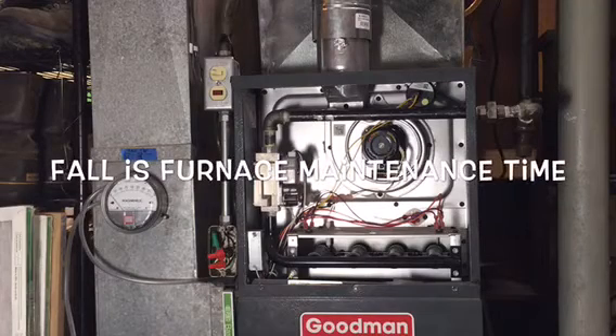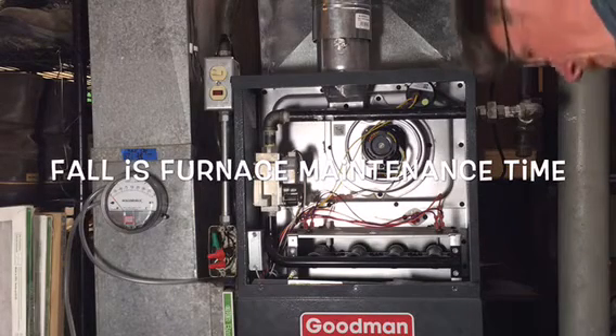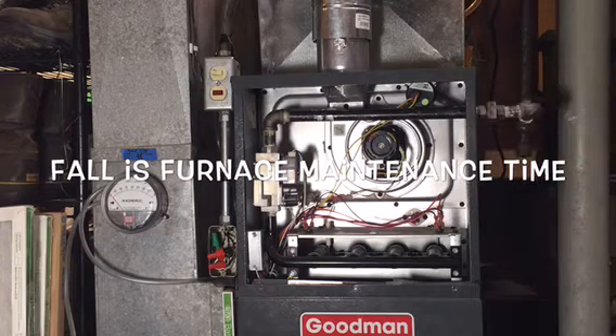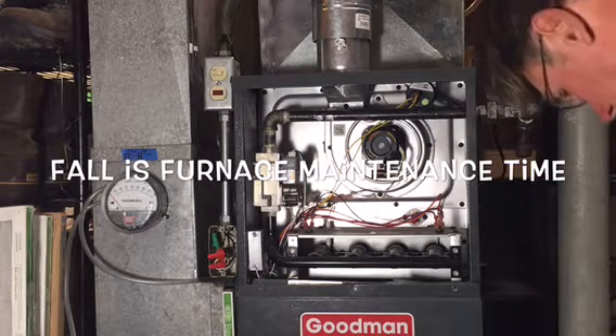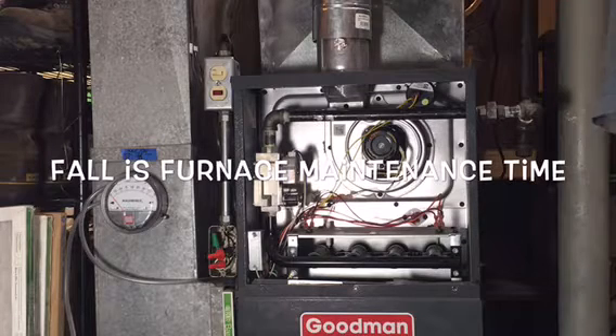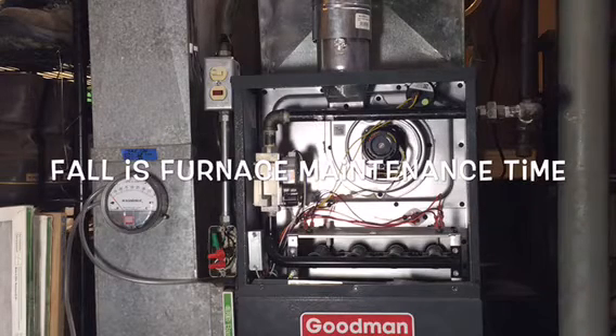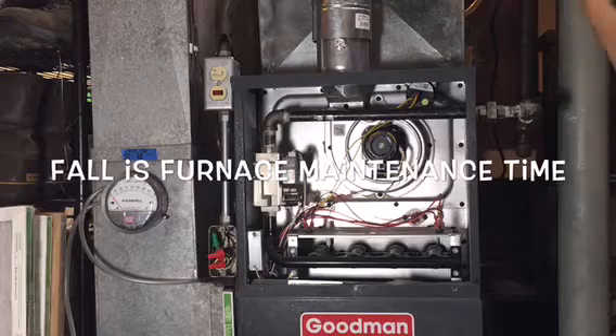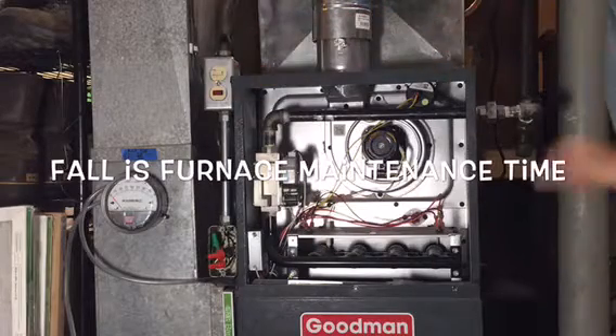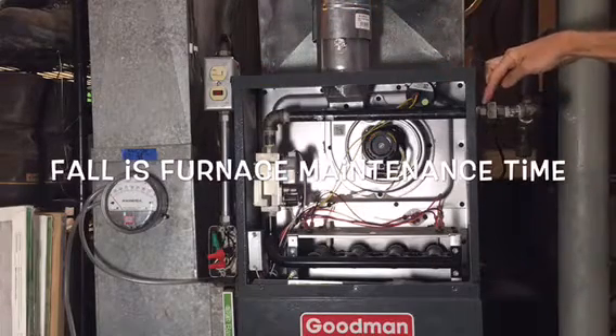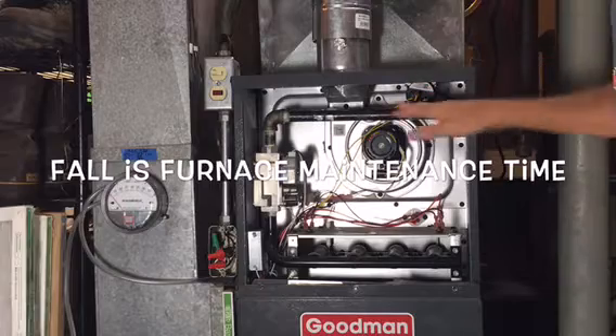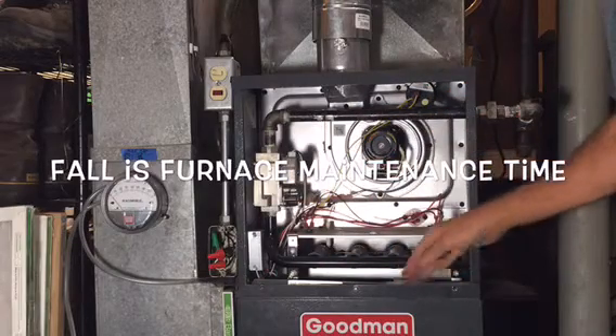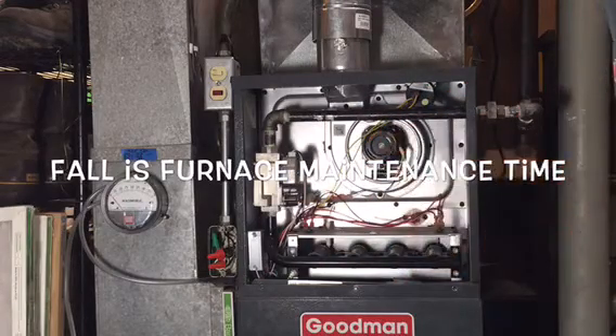Okay, we're about to start the annual furnace service here. We've opened up the front cabinet. This is a medium efficiency 80,000 BTU Goodman. We've also made sure we've turned the gas off and the power is off the unit. Now we're going to open up the union, which will allow us to unbolt the manifold, the gas manifold, and get to the burners here.